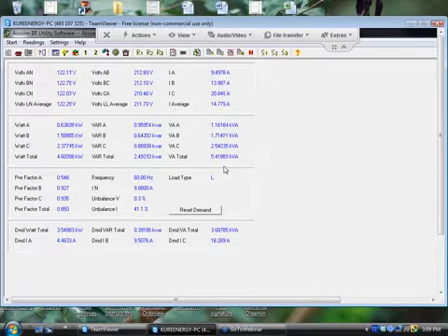Con Edison, one of the largest power companies in America, last year introduced a new reactive kVA power demand charge. They said on their site that if you raise power factor up to 95%, well here we are without our energy-saving components working, at about 85% power factor average total. If you can raise it up to 95%, you can eliminate our demand charge. If not, that demand charge equals close to 10% of the entire bill. That's how much people's bills went up just because of the demand charge.